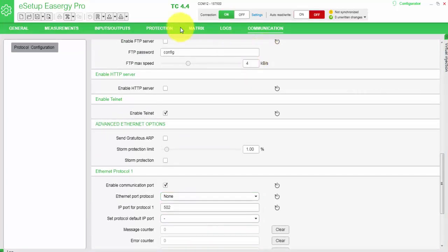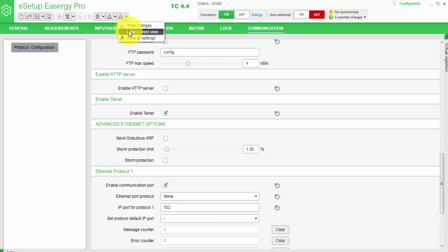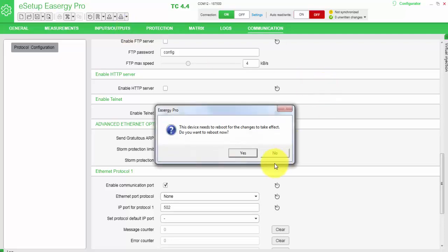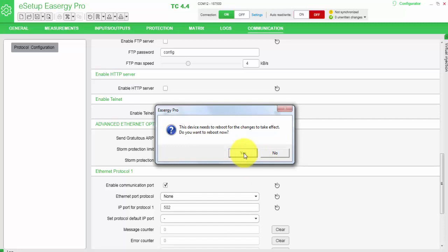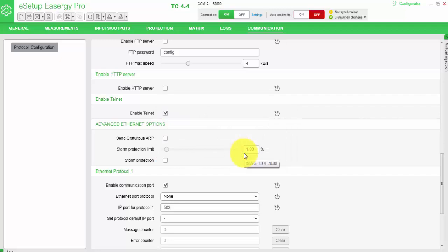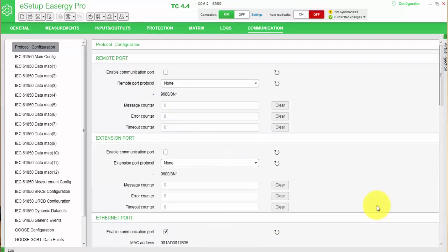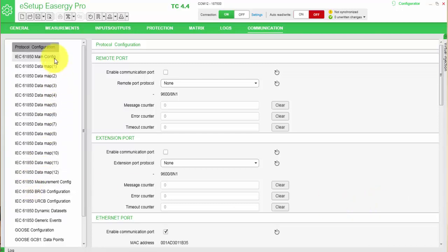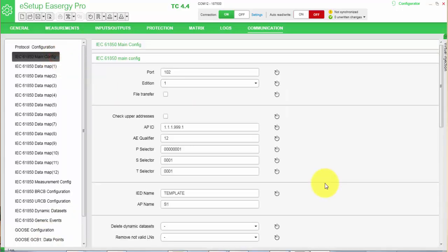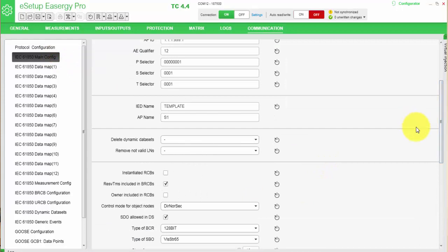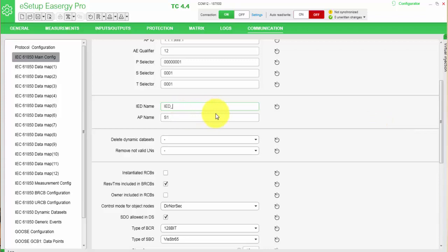After that, I need to send the changes or the selection of the protocol to the relay, and the relay will ask approval for reboot, and we have to answer yes in order to activate the menus we need to further configure. After the relay rebooting and re-reading the view, we can find a lot of new menus based on our protocol choice. So the first menu to go to is IEC 61850 main configuration. The most important parameter here is the IED name, so I will give the name IED_1.